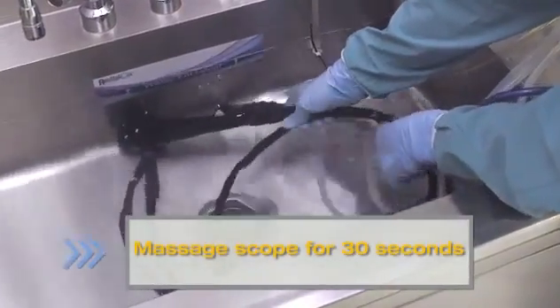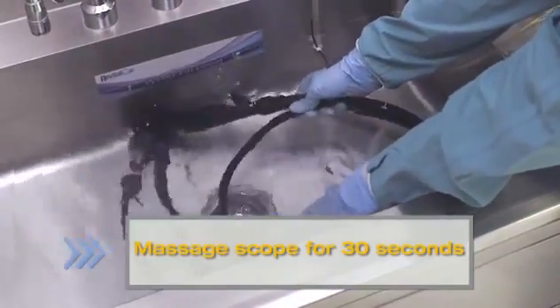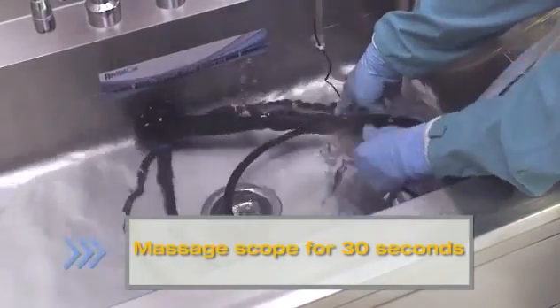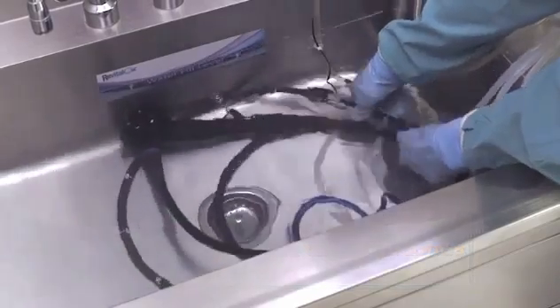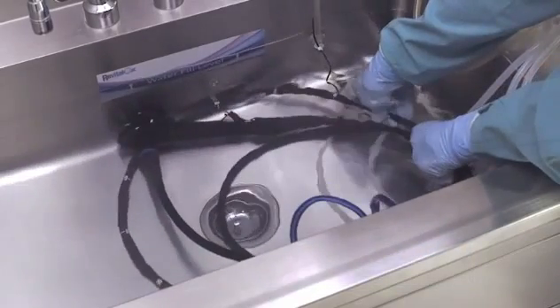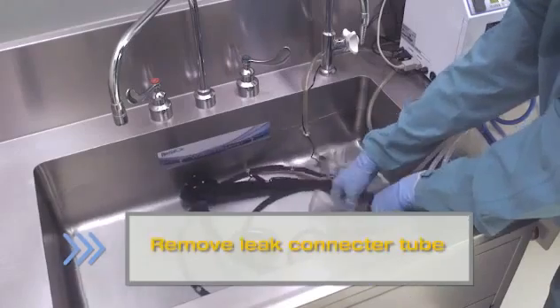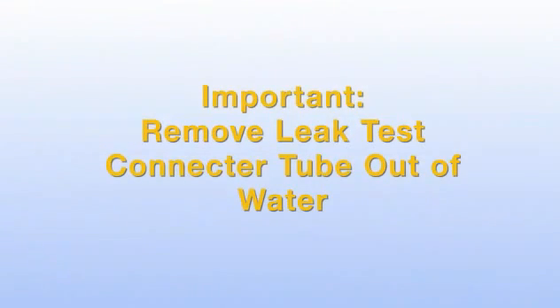Press Enter to deflate, and then be sure to massage and angulate the scope for approximately 30 seconds when deflating to remove any existing air from the scope. Once deflated, remove the leak test connector tube and place on the watertight cap if required. If bubbles are detected, follow the scope manufacturer's IFU for further processing requirements.